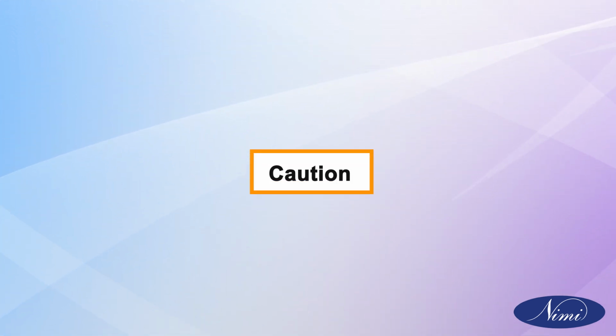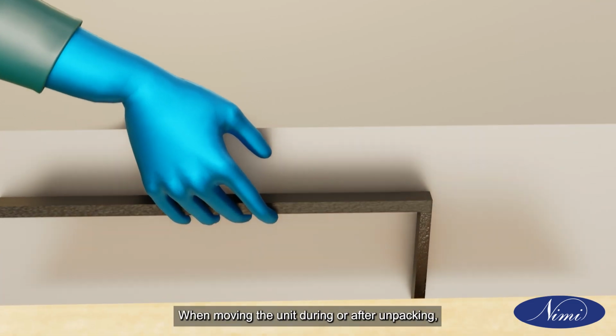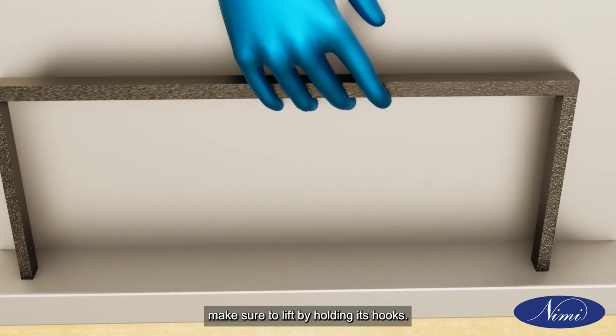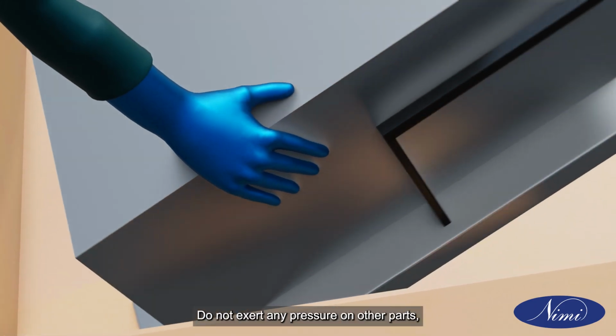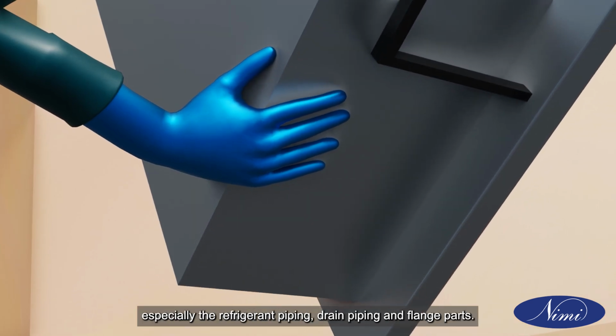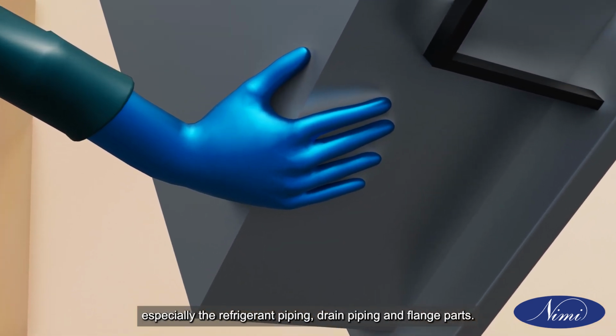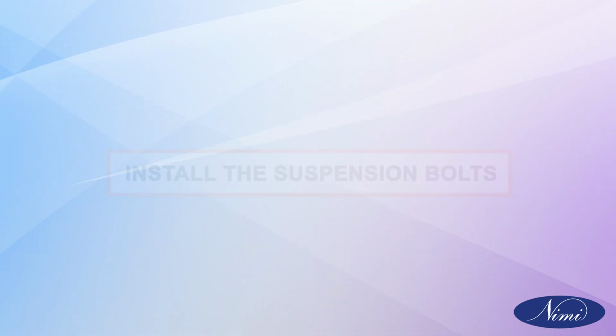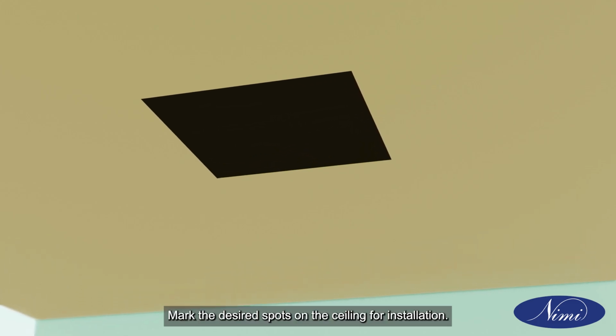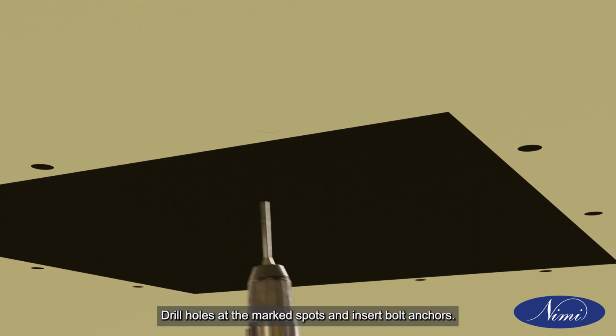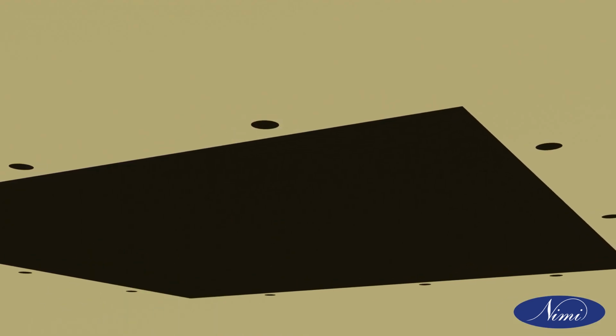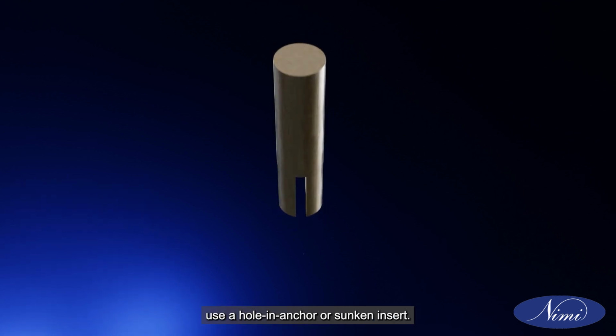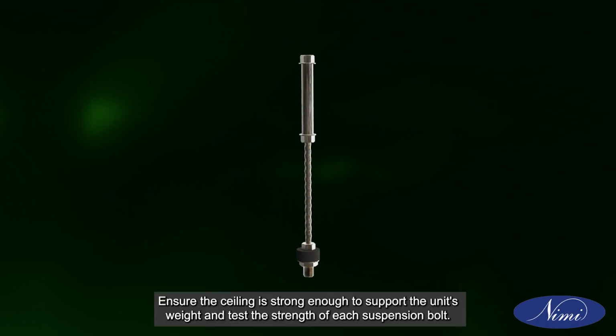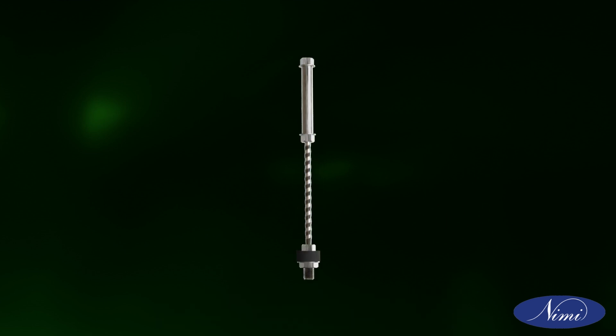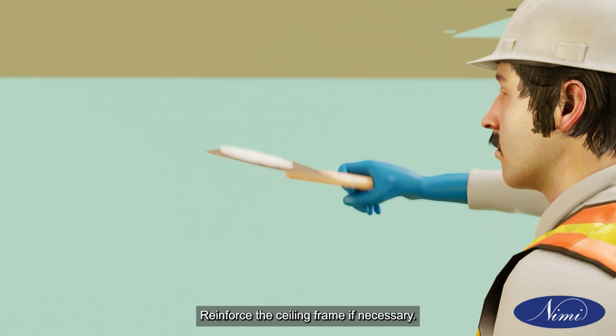Installation. Caution: when moving the unit during or after unpacking, make sure to lift by holding its hooks. Do not exert any pressure on other parts, especially the refrigerant piping, drain piping, and flange parts. Install the suspension bolts. Mark the desired spots on the ceiling for installation. Drill holes at the marked spots and insert bolt anchors. For existing ceilings, use a hole-in anchor or sunken insert. Ensure the ceiling is strong enough to support the unit's weight and test the strength of each suspension bolt. Reinforce the ceiling frame if necessary.